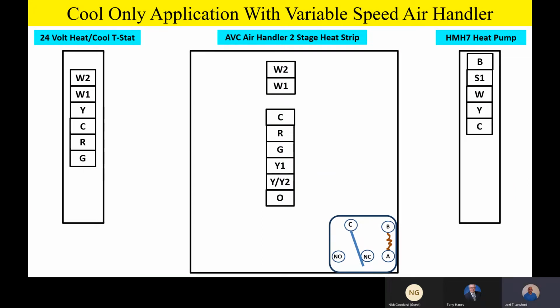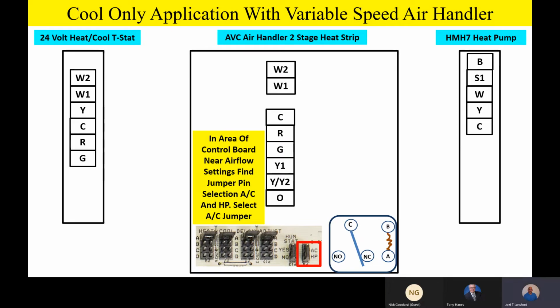So if we have a variable speed air handler, and this is important, we're not going to take the B outside. In the area of the control board itself, there's going to be a setting. If you look near the airflow settings, you're going to find a jumper that says AC and heat pump. Even though it's a heat pump outside, we want to trick the air handler into thinking it's not a heat pump outside, it's straight cooling.